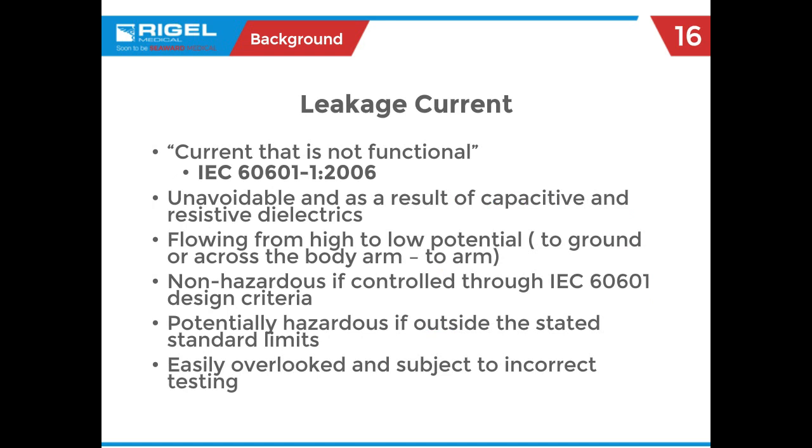Leakage current is current that is not functional — the bad current. It's called different things in different places. It's always going to be there — anytime you measure zero leakage current, you raise an eyebrow. It is a result of capacitance, resistance, and even inductance as part of the circuitry. If not controlled by the specifications of IEC 60601 or the AAMI equivalent, it can get to the point where it harms the patient. That's why we have limits and test to ensure products are within those limits.